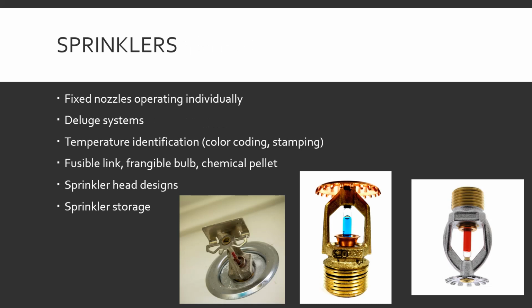Fixed nozzles operating individually. Just talked about the forklift scenario. That's kind of what this is. Forklift is driving around. It's a sprinkler head. You go there because there's a water flow alarm. The alarm company called, or the building called, said, yeah, we have a sprinkler going off. Can you come take care of it? You go in. There's a forklift parked there, and there's one sprinkler spraying water everywhere. That's the fixed nozzle operating individually, where the nozzle itself has to trip for water to come out. So the fusible link has to break, the frangible bulb has to break, that kind of thing.